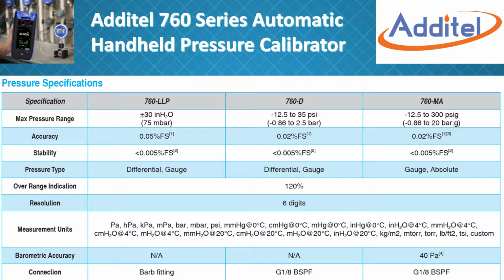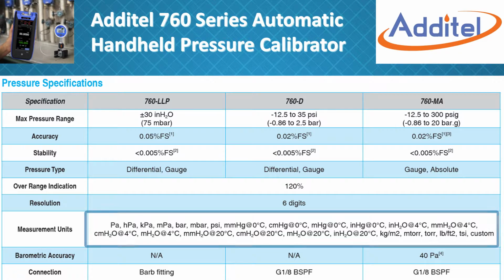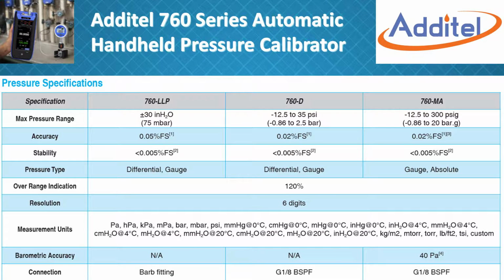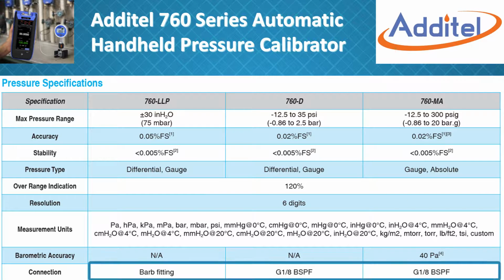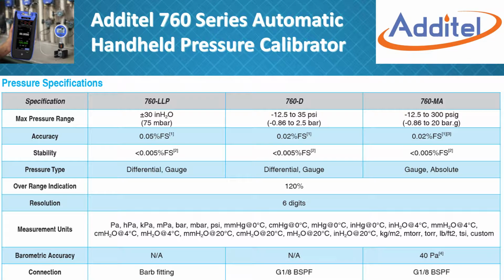120% of overrange, 6-digit resolution, plenty of engineering units, different measurement units that you can use. And as it says there, barometric accuracy is 40 pascals for the 760MA module. The connection type's barb fitting, which is very common for low inches of water ranges, and it's a BSP, I think, comes natively on the 2 high pressure units. However, it comes with an adapter kit, so you can change that to NPT and also metric threads, I believe.